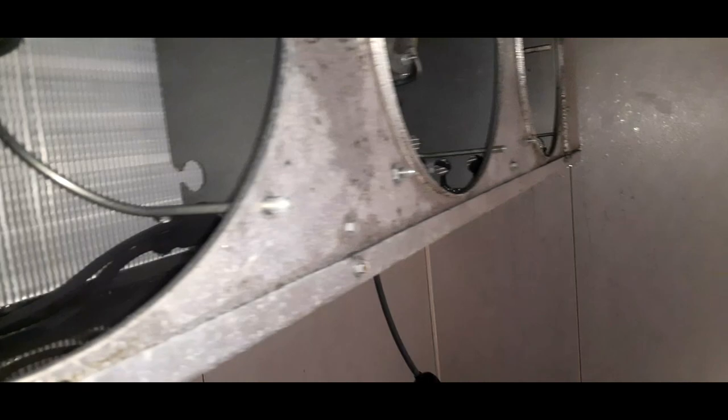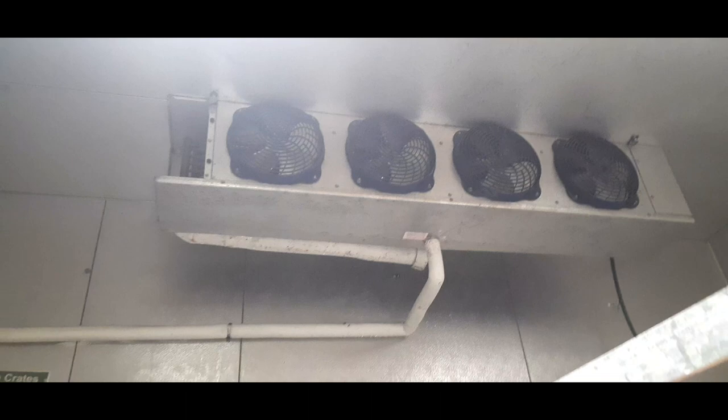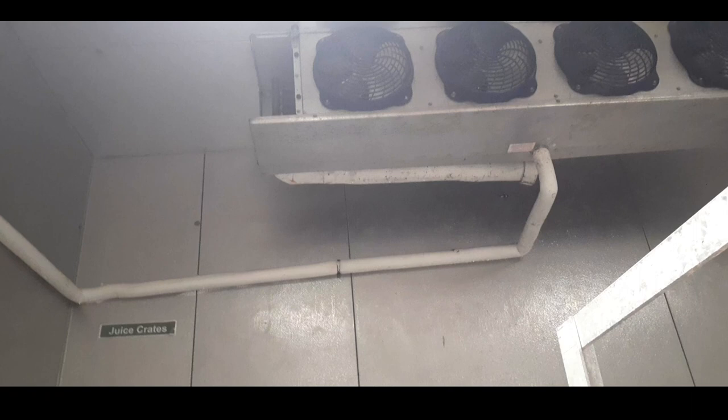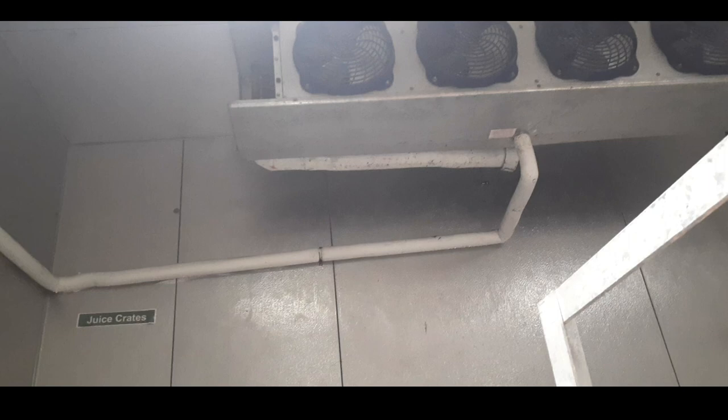All right, we're all done. Let's get our blades back on. Also, we're going to check our solenoid for our glycol to see if there's still flow. This coil will be getting cold. So I just put my fan blades back together. I believe this unit froze up due to the drain line being clogged. This is a glycol case. Normally what it does is has a solenoid that stops the flow of glycol when it goes to defrost, so there's a time-off defrost cycle.